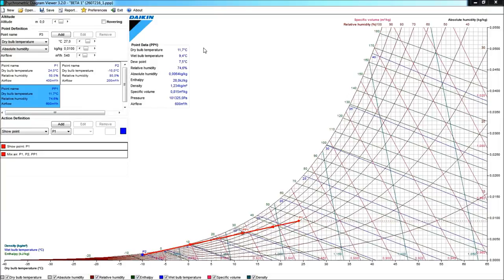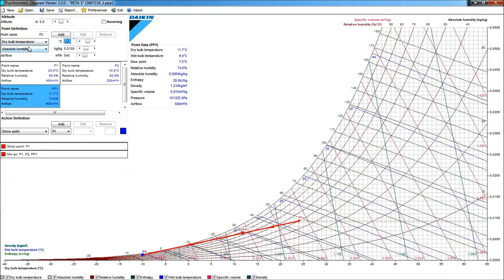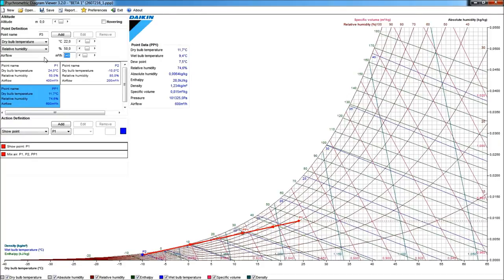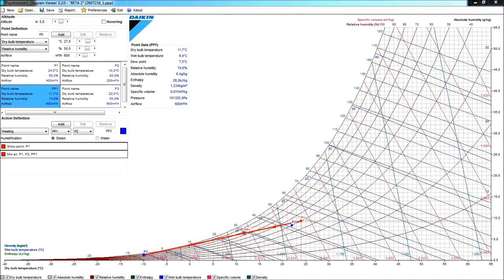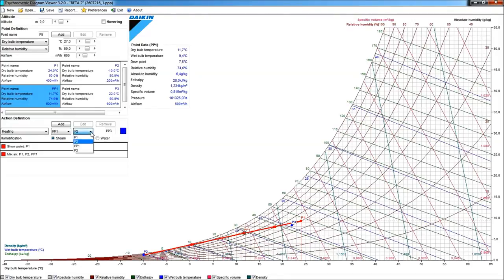My room, by the way, I would need a room condition that I didn't specify yet, and let me specify this to a temperature of 22 degrees with a relative humidity of 50%. And I will need, of course, to enter 600 cubic meters per hour now, because this would be the sum of my return air and my fresh air. So, if I add this, I'm getting the point P3 in my diagram now. What is now definitely required is to have a heating action between the point PP1 and my desired room condition P3.